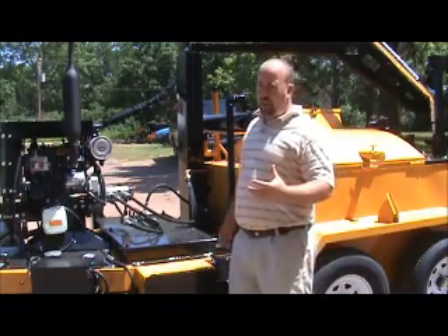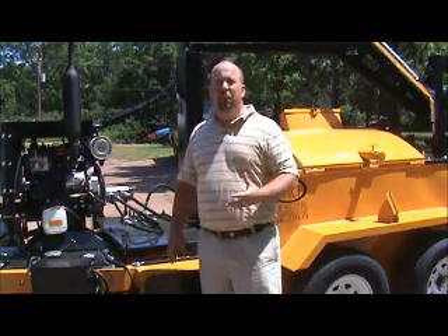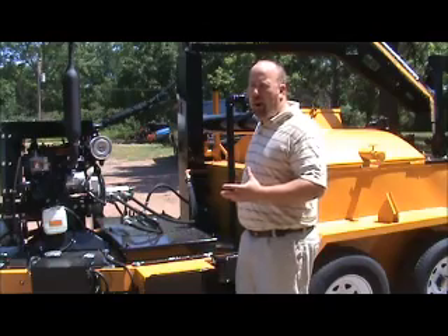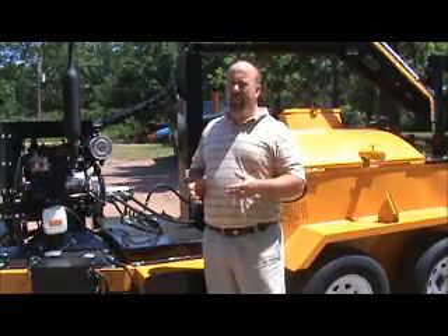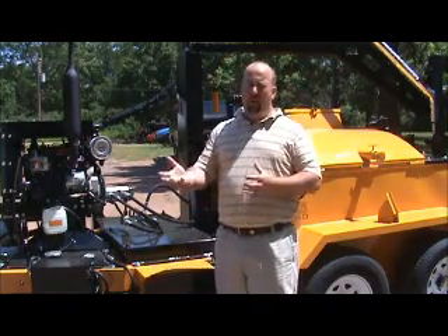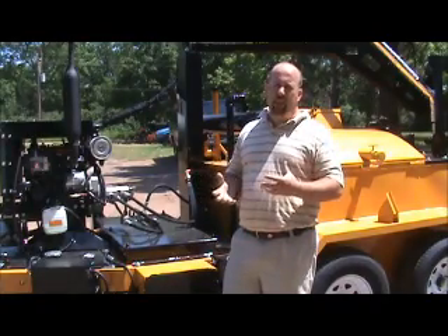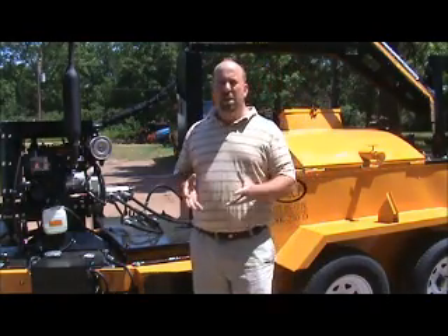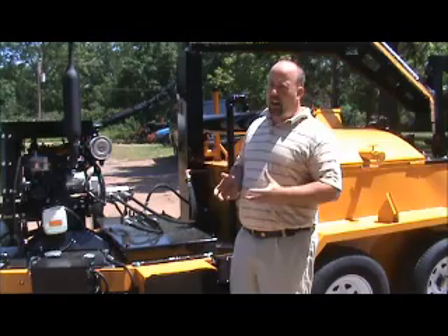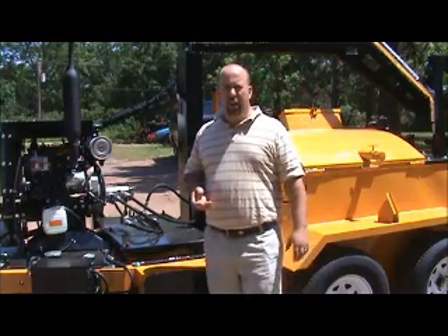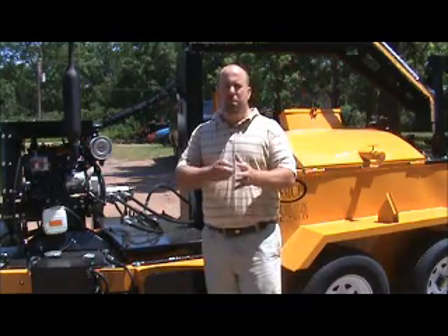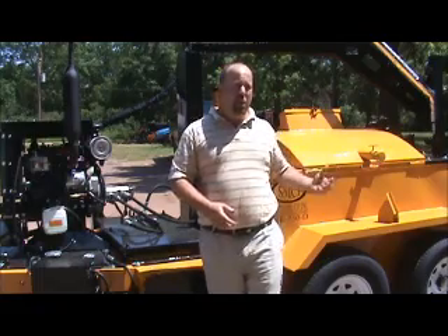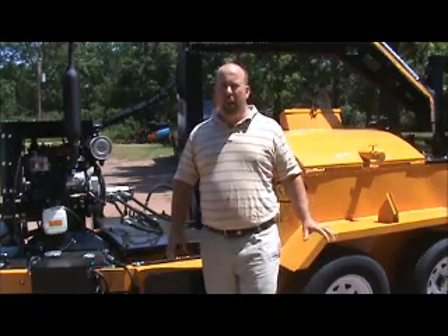That does us a couple of things. It extends the life of our tank. Your tank is never going to burn out. Some of the other kettles and some of the other manufacturers actually fire the burner onto the bottom of the tank. You have that intense heating and cooling always happening on the tank. I always like to explain it kind of like a torch. When you put a torch on a piece of metal, you'll see it start to flake. Well, that's what it does to the bottom of the kettle if we fire on that.